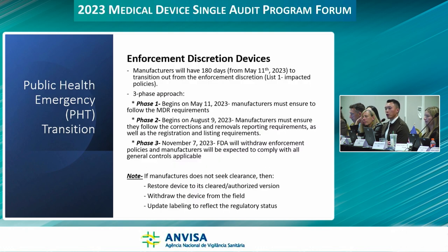So the three-phase approach: phase one begins May 11th. Phase two began on August 9th, which requires manufacturers to ensure they follow the corrections or removals reporting requirements for recalls, as well as registration and listing requirements. Phase three, November 7th, FDA will withdraw enforcement policies, and manufacturers will be expected to comply with all general controls applicable for their device.